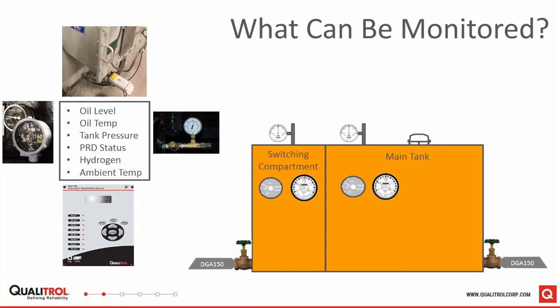If you're interested in monitoring your temperature or your oil level, which are very important things, the temperature and oil level gauges can be easily removed and replaced with gauges that have analog outputs that can be fed to a 509 or a QTMS or other equipment. Normally there are 2 or 4 screws that can be removed to remove the existing gauge. Temperature gauges a lot of times are direct mount gauges that you just unscrew out of the well, and then you can install the replacement gauge right back into the well.